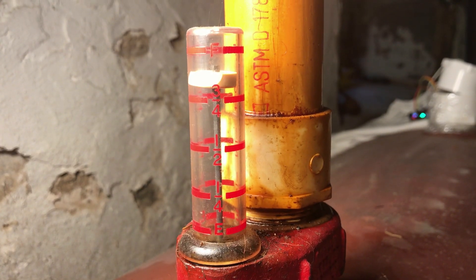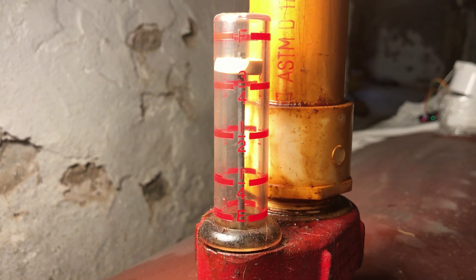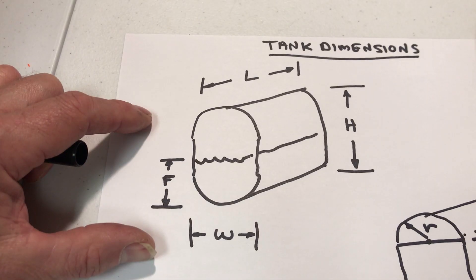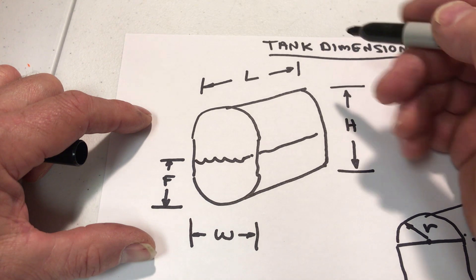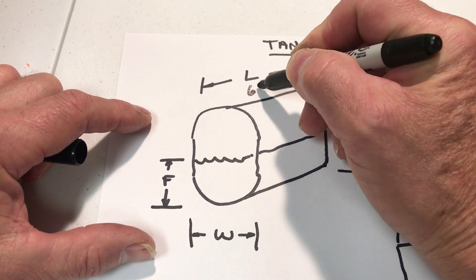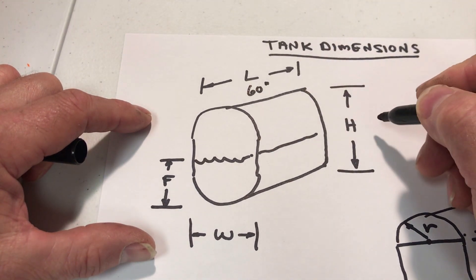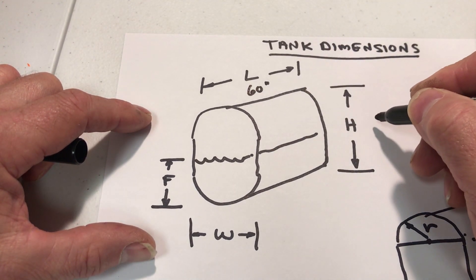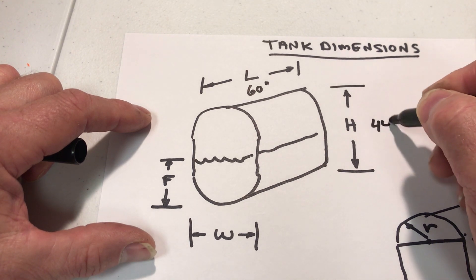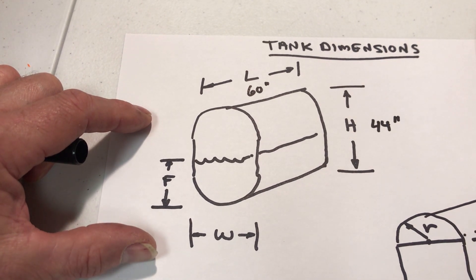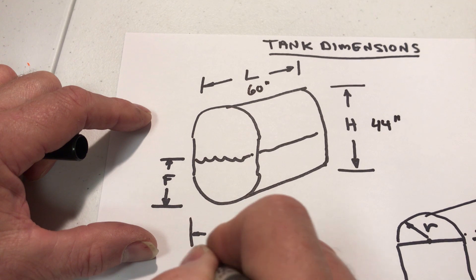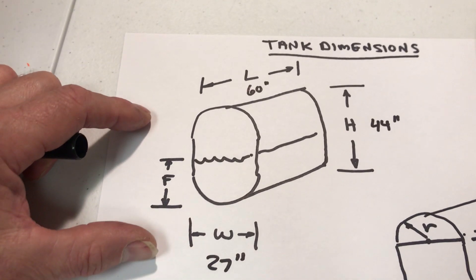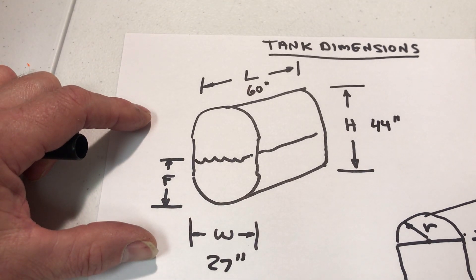The other approach is to determine the underlying equations. To measure the number of gallons in the tank, we need to know some dimensions of the tank. So the length of the tank is 60 inches, the height is 44 inches, and the width is 27 inches for a 275-gallon vertical tank.